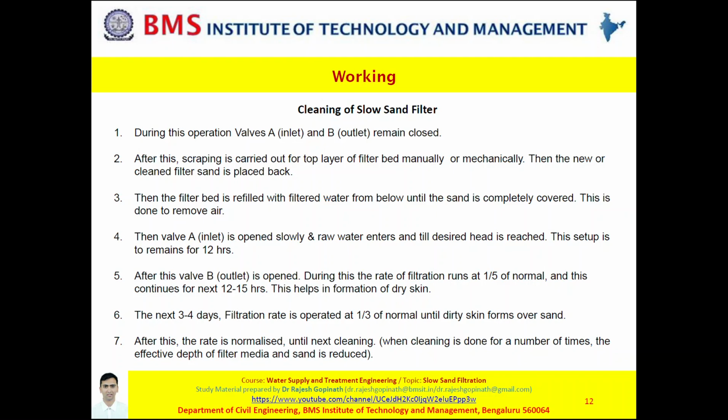Therefore, it is imperative that when a slow sand filter is being cleaned, you need to have a standby which does its function. During the cleaning of a slow sand filter, the first thing you need to do is close valve A and valve B, which means neither the raw water enters and there is no scope for any water to go out.